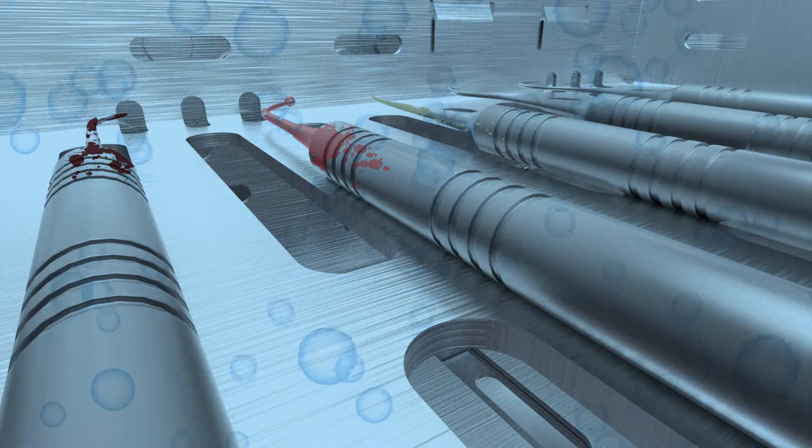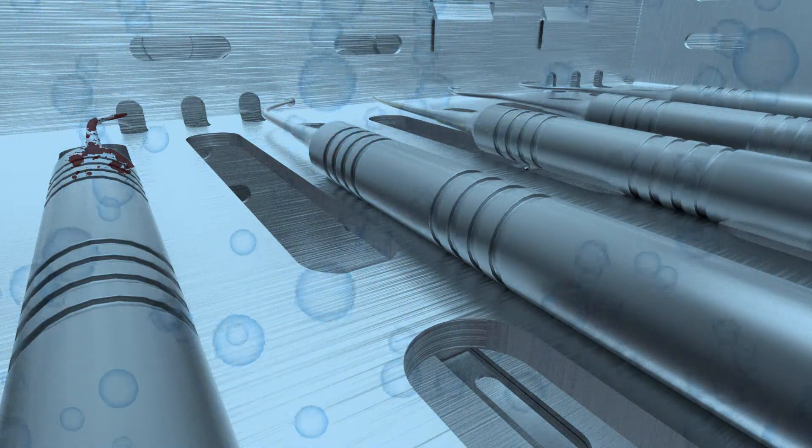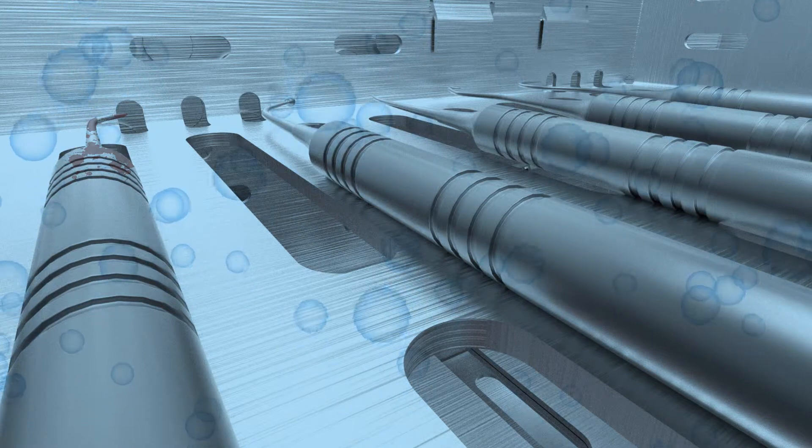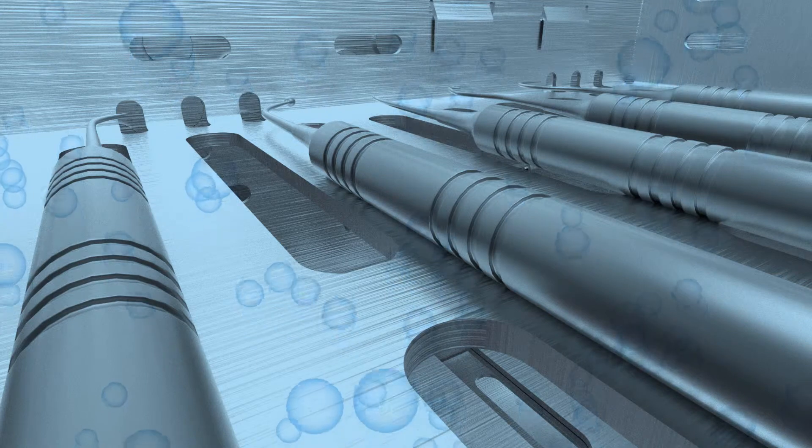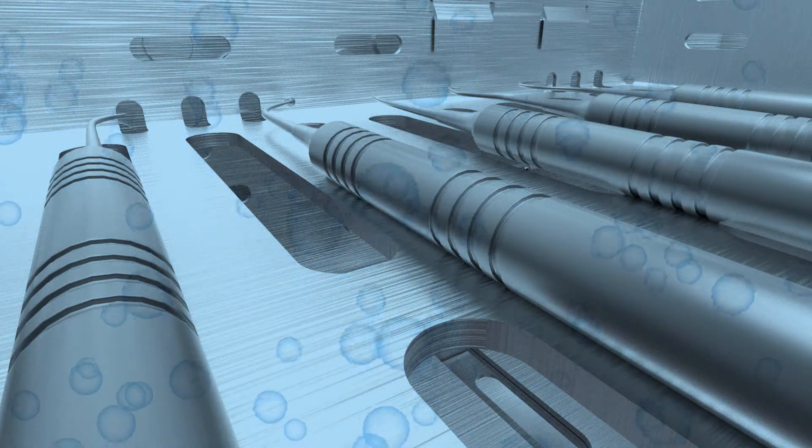During cavitation, millions of tiny bubbles form and then collapse or implode, releasing enormous amounts of energy and shock waves which scour the surface of instruments, appliances, and other devices placed in the cleaning solution.